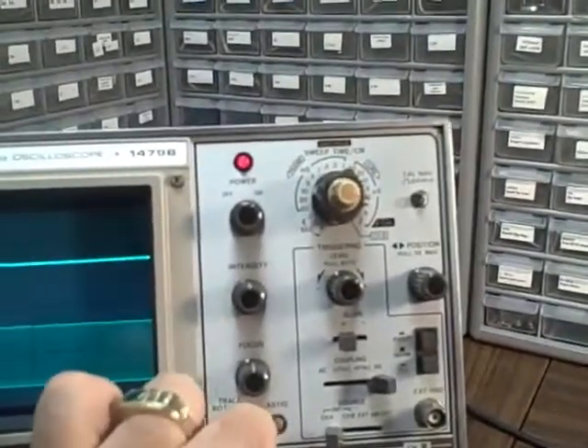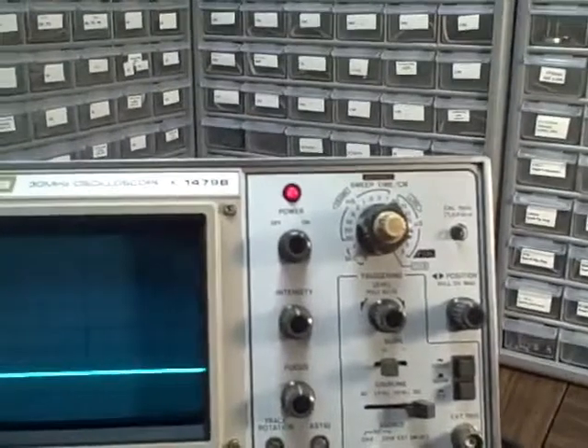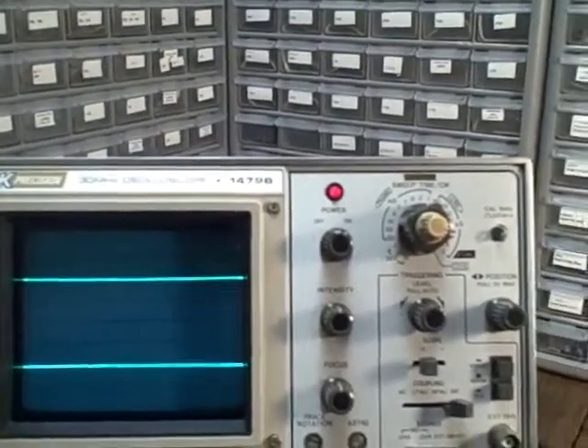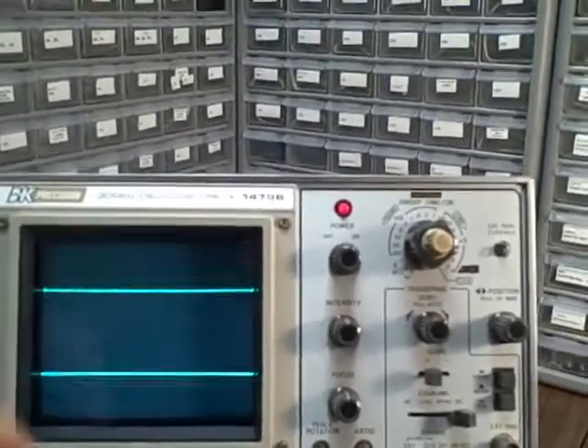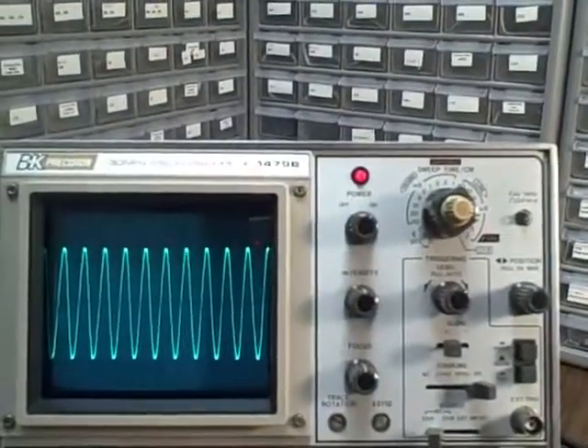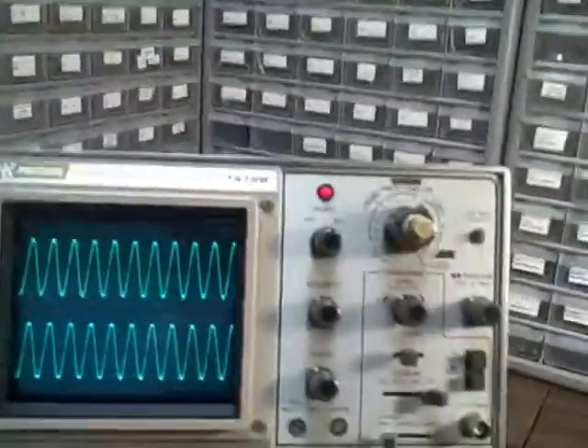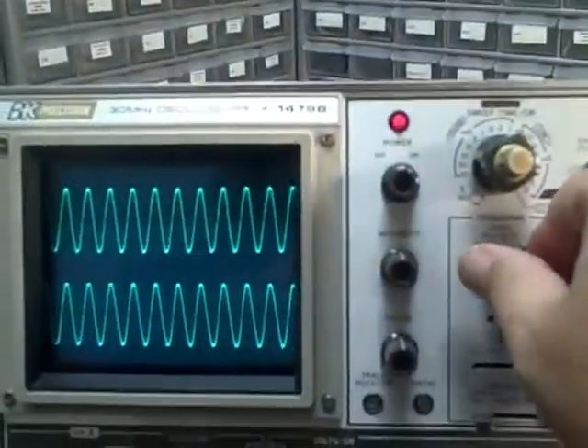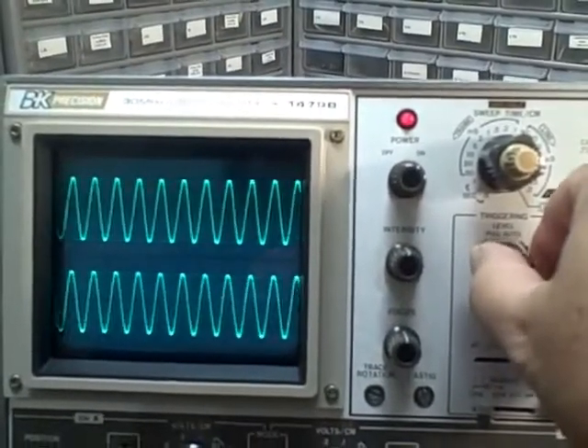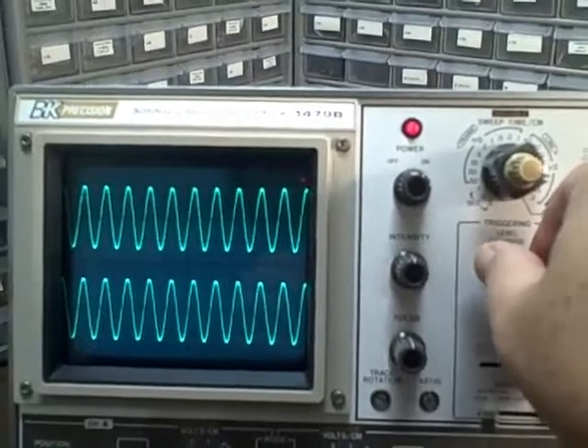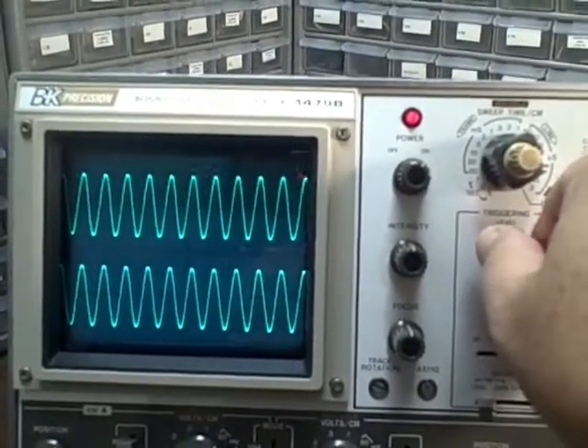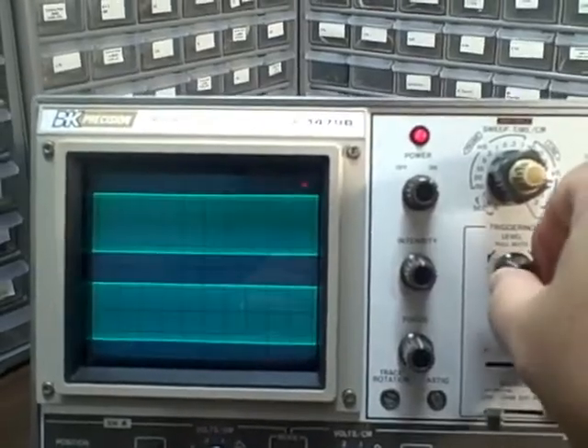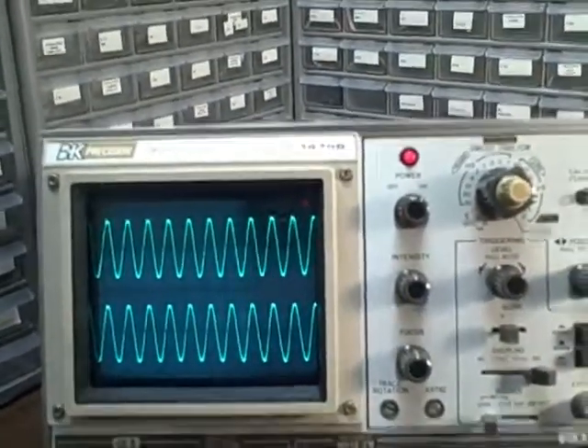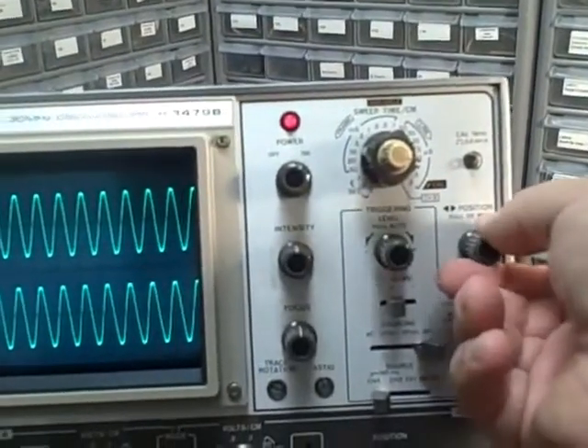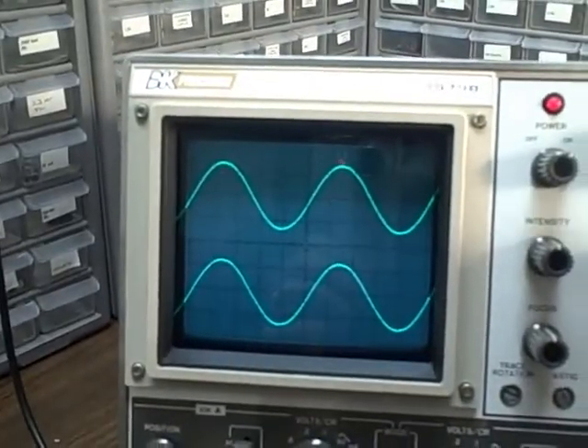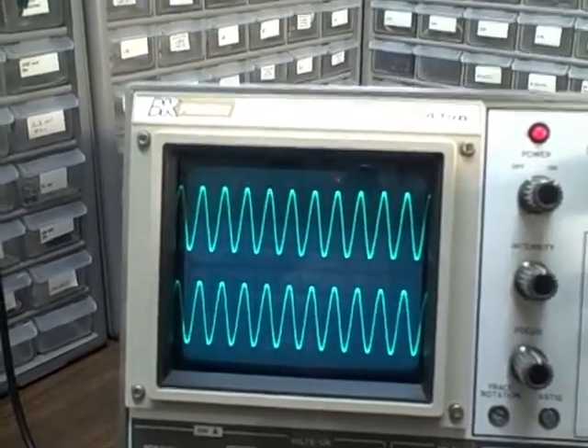All the switches are functioning properly, as I'm saying here. There's channel B, channel A, both channels, additive. Let's put the signal back on it. We have the sync adjustment. We are in auto right now. Here's normal, no sync, adjusted sync, no sync. Back to auto. That's normal. We have a ×5 magnification for horizontal. Working well.